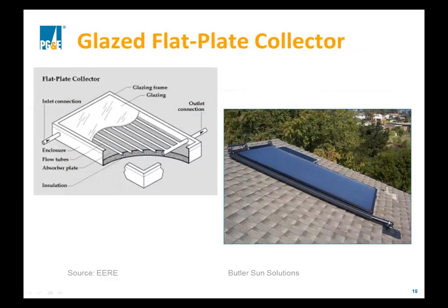What we see quite a bit of for domestic hot water heating are glazed flat plate collectors. These have copper absorbers inside of an insulated package with a glazing that maintains some heat inside and reduces some of the thermal losses that those previous polymer collectors can see. So these are capable of generating higher temperatures, and I think is what we've seen most commonly in the program so far. Next slide.